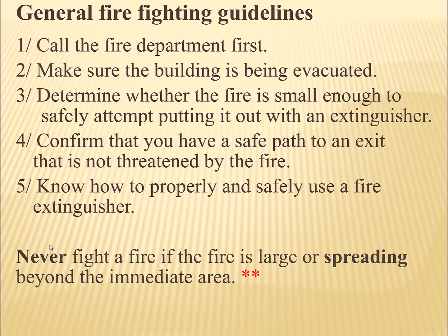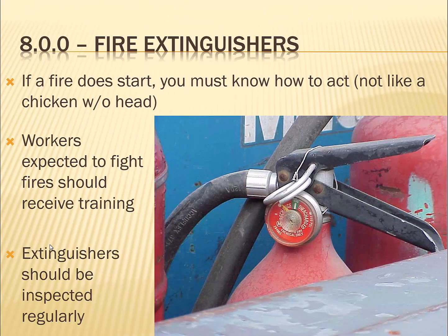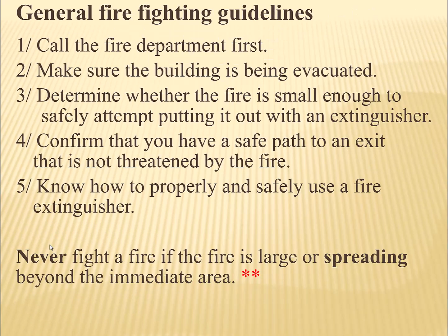Okay, so you never fight a fire if the fire is large and spreading beyond the immediate area. You've got to make a judgment call. But here's the thing: these extinguishers just don't last that long. You get about a second or two per pound, and so you better aim wisely at the base of the fire before you ever pull that trigger, and then be prepared to move that fire extinguisher because you may not aim quite right. You're shooting from the hip. It's not like you got gun sights on this thing.